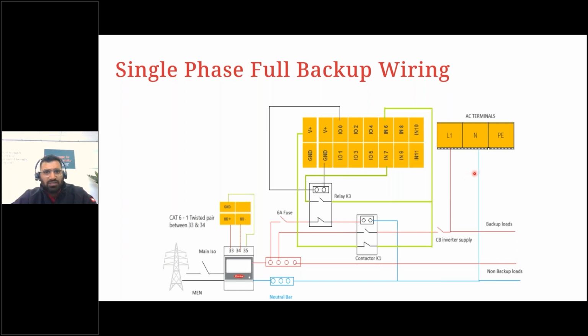This is very basic, very simple connections. If you look at it, it is just 5 connections on the digital I/O plug. IO0 and ground is just the power supply for the relay, and IN6 is feedback from the contactor, IN7 is feedback from the relay, and V+ is where you can get the 12 volt to supply the contactor and relay and get the feedback at the inverter.